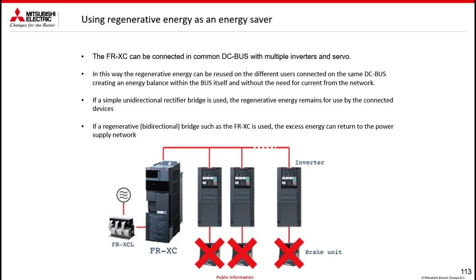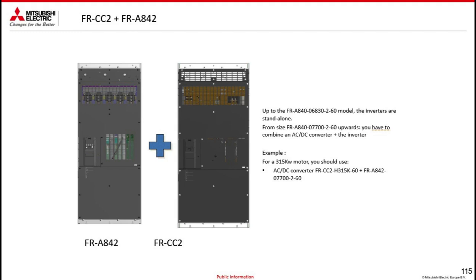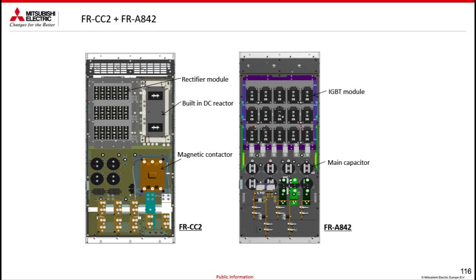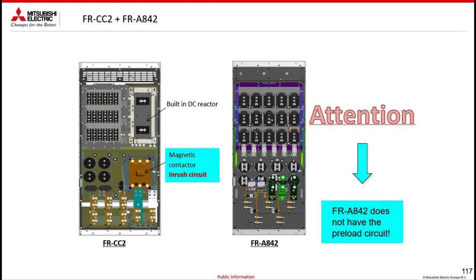Another option could be to use the common DC bus, also for energy saving, where you use an FRXC, which is nothing more than a bidirectional converter. It converts from AC to DC and powers all the inverters directly in DC, and if there were any regeneration problems and the voltage goes beyond a certain value, it reconverts from DC to AC to put the energy back in the net. I won't go into too much detail here, but these are details you might want to know when you're interested in the configuration possibilities for the external unit, the A842.